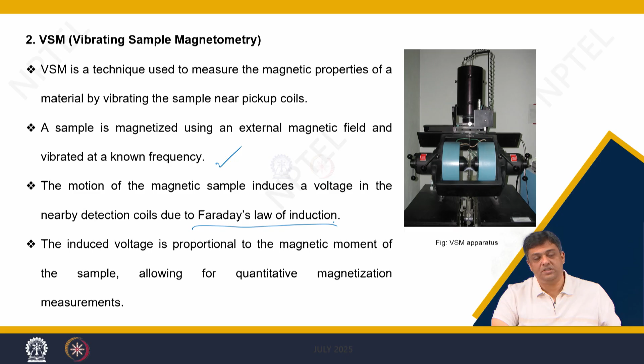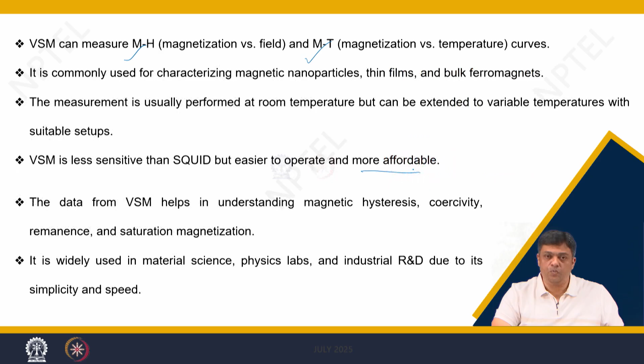Here also you can carry out MH curves or you can have MT curves. This technique can be used for nanoparticles, thin films or even bulk ferromagnets. Generally, VSM is performed at room temperature, but nowadays you have such systems where you can carry out measurements at low temperatures as well as slightly higher temperatures than room temperature. VSM, as you may have seen, is not using superconducting coils or anything like that. So, it is less sensitive than SQUID, but it is easier to operate and less expensive. So, it becomes more affordable. And using the measurements, you can then draw the magnetic hysteresis loop. From there, you can find out the coercivity, remanence or saturation magnetization. And this is one of the most common techniques which are used to determine the magnetic properties of the materials we are discussing in this week.